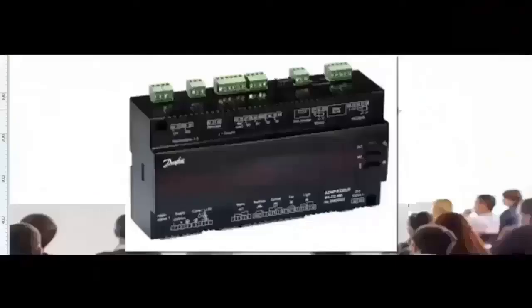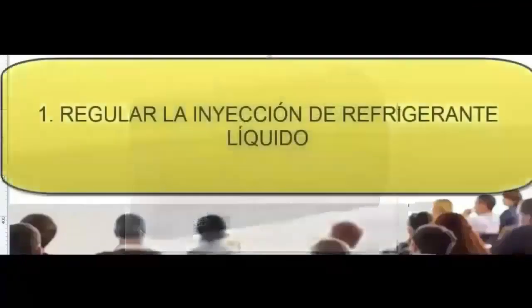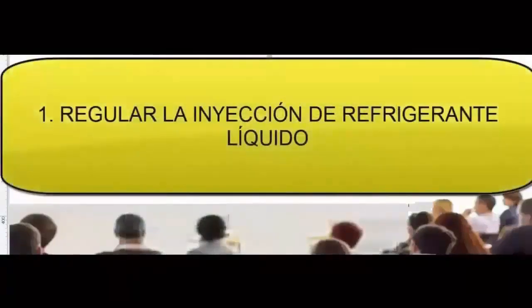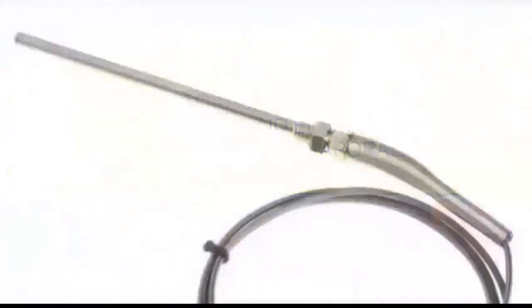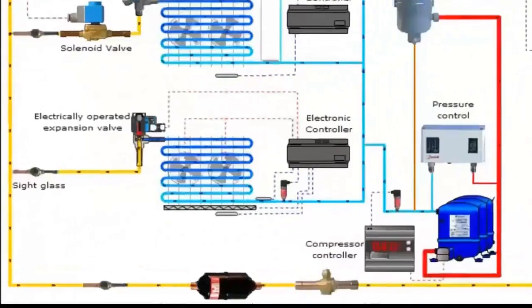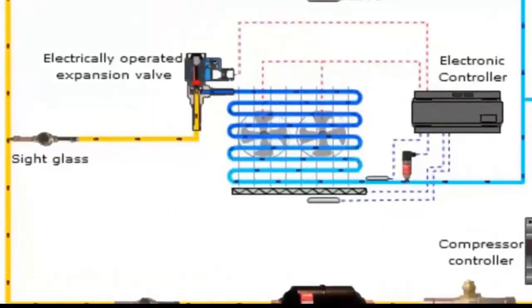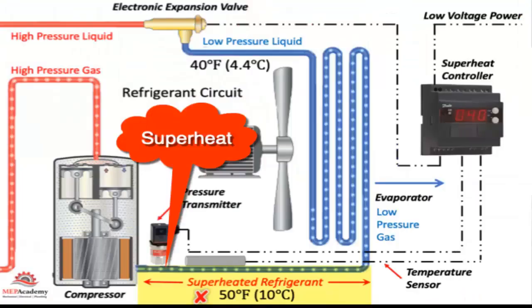The main function of the electronic controller for the evaporator is to regulate the injection of liquid refrigerant into the evaporator. The supplied liquid refrigerant is controlled by a signal from temperature sensors or with a pressure transmitter. When working with an expansion valve of the AKV type or of total opening and closing, the evaporator controller decides according to the reading of the sensors the time that the refrigerant must be allowed to pass to the evaporator. The controller opens and closes the AKV valve. Based on the sensor readings, the valve opening is independently adjusted so that the evaporator provides the optimum amount of refrigerant at all times. By using a pressure sensor and a temperature sensor, correct measurement of the refrigerant superheat is achieved in any condition, which ensures very precise and robust control.